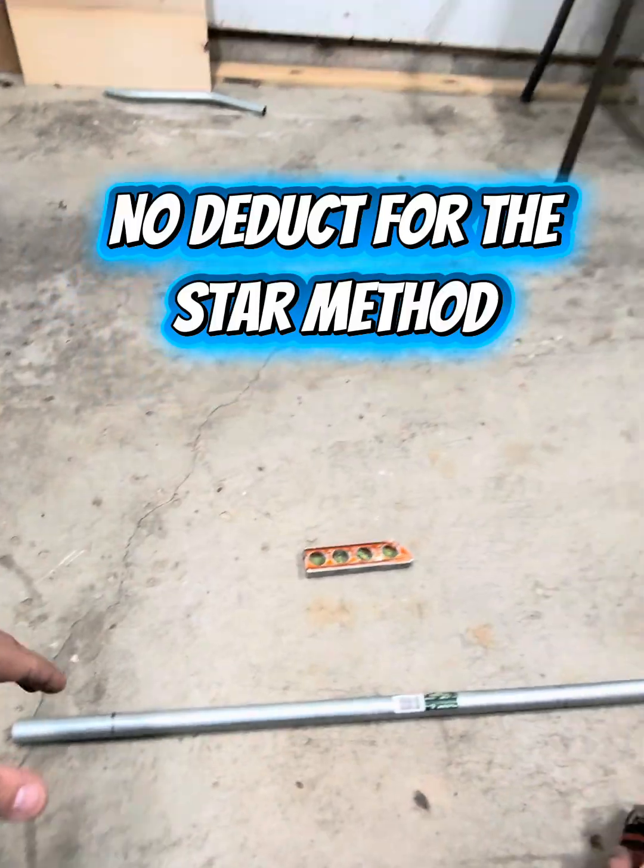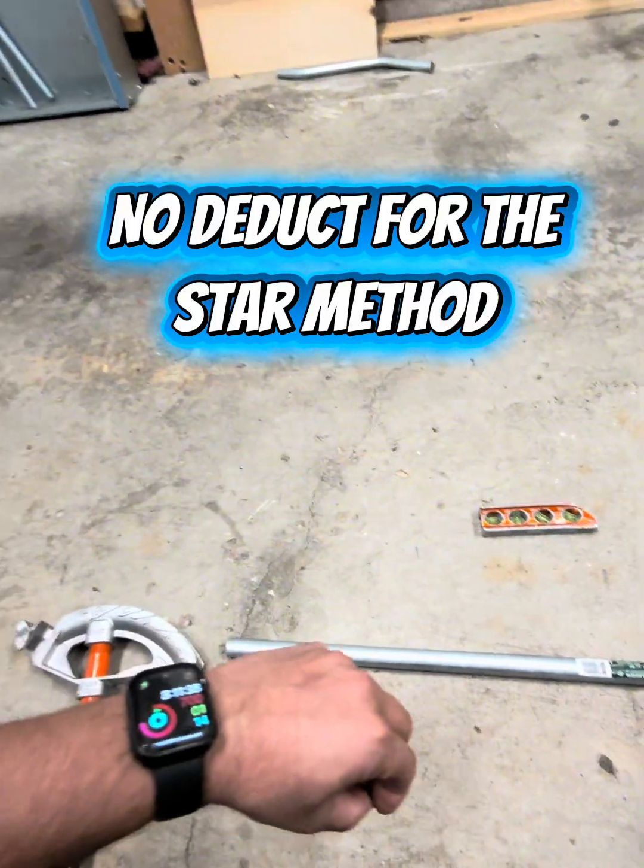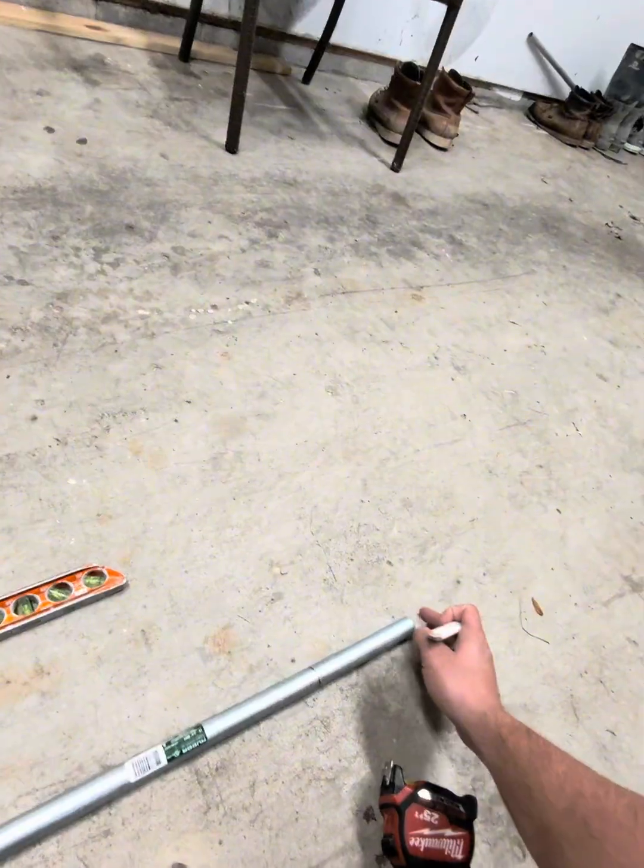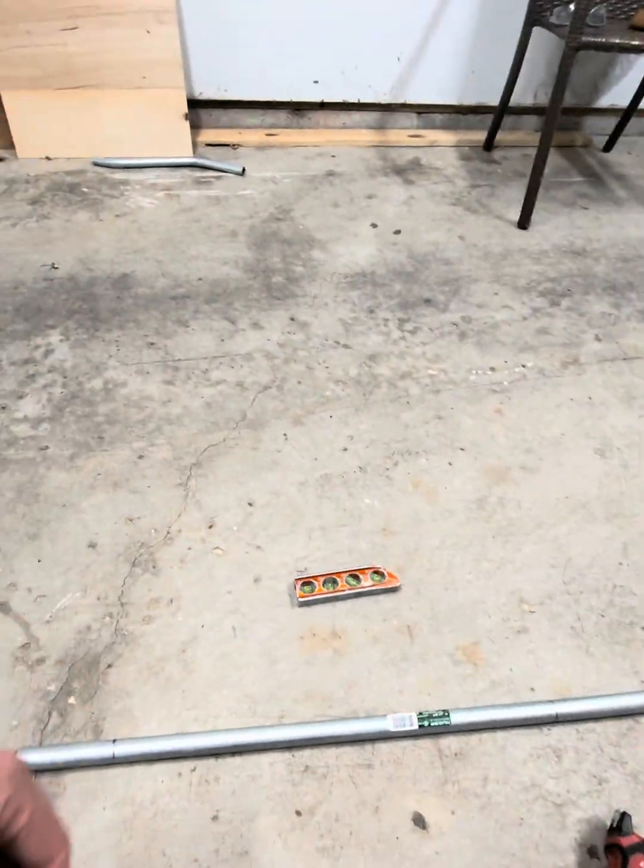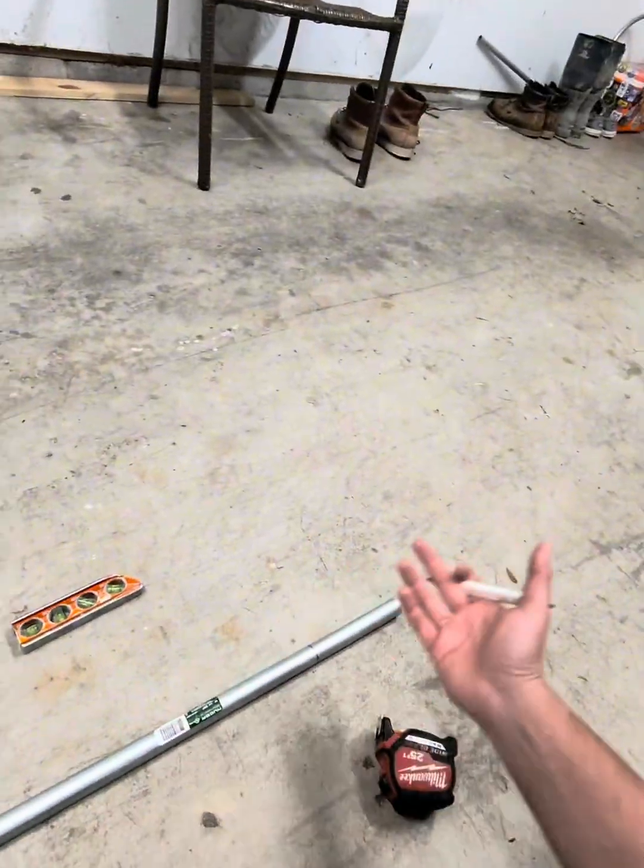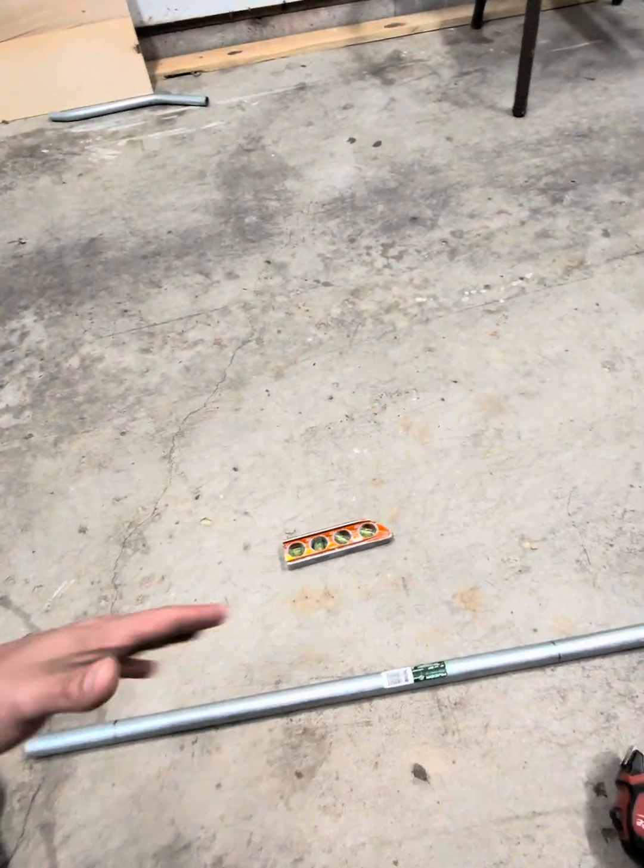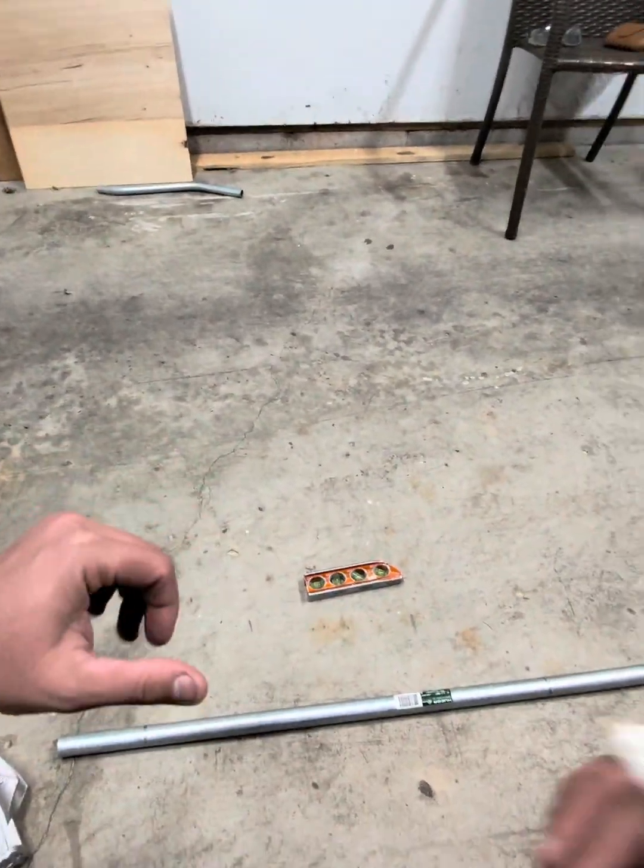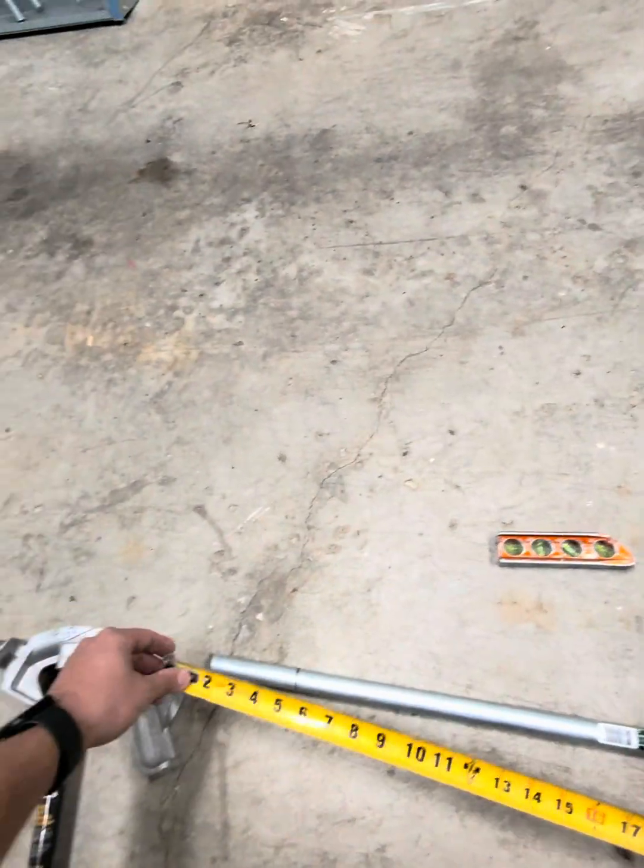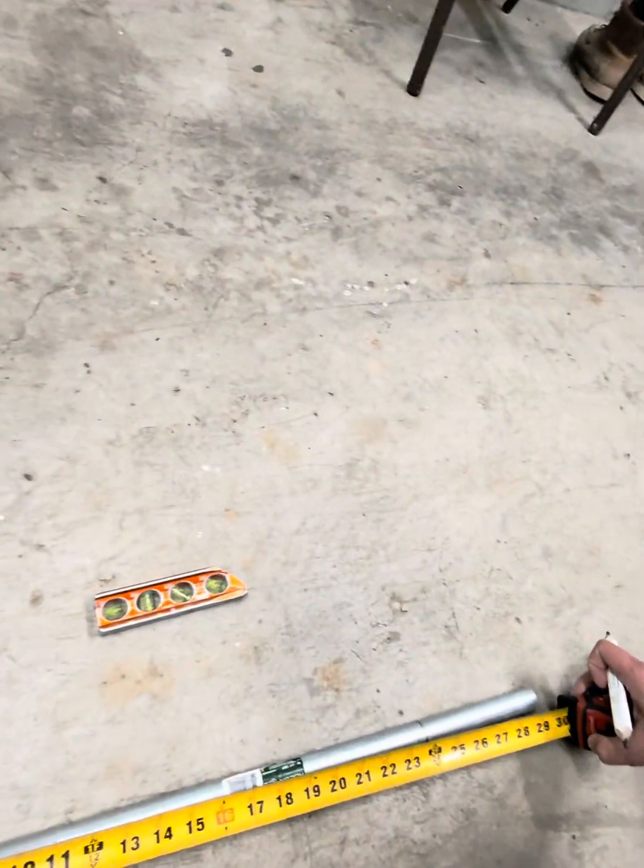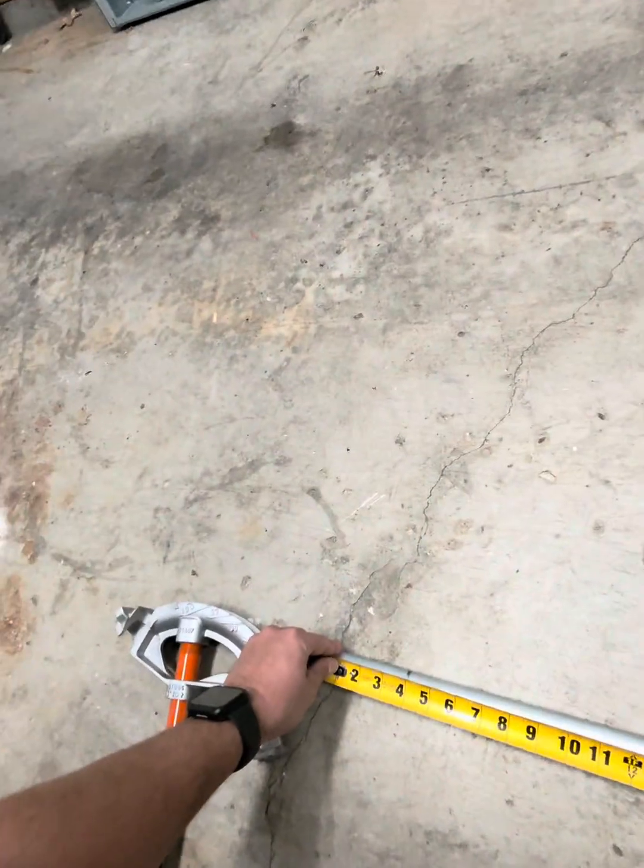So with the star method, there is zero deduct. Let me just say we have a 29 and a half inch piece of conduit, and I say hey Rob, that's my imaginary friend over there, I need a 24 inch 90 off that piece you have there. What are you going to do? So I say 24 inch 90 on the star method. This is when this would come into play. The star method has zero deduct. There is no deduct.